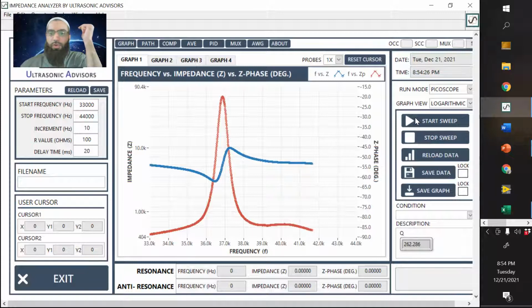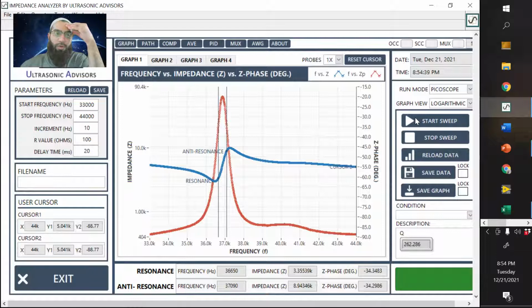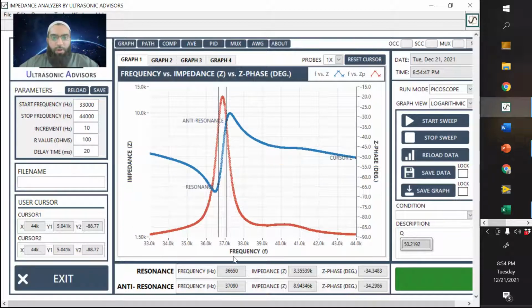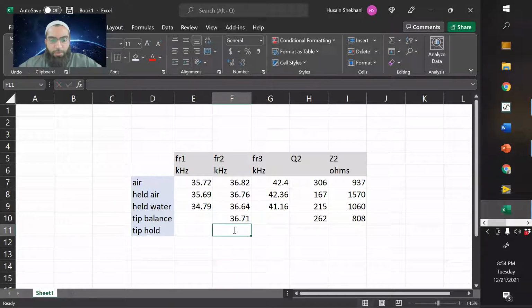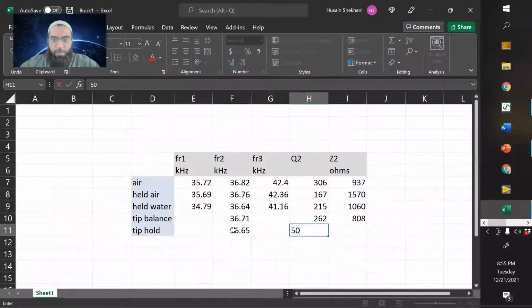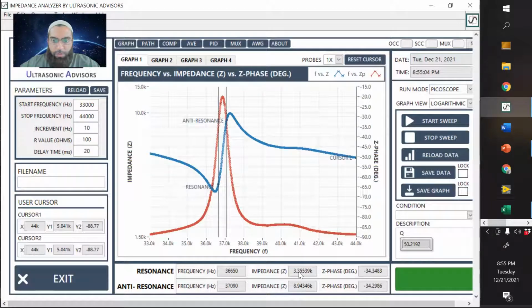So for a real resonant device, if you just hold the tip with your fingers, you shouldn't be able to destroy, like completely eliminate the resonance. So I would say that 42 kilohertz is not the real operation point. Just holding the tip should not be able to completely eliminate it, even though it is heavy damping. Like right now, we're at Q of 50, and the resonant frequency is 36.650 when I held the tip. So 36.650, and the Q is 50, and the impedance is 3.35.